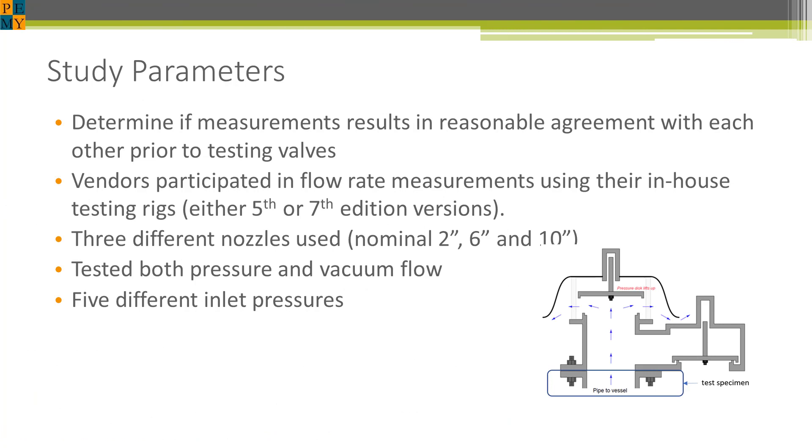Here you can see the flow nozzle that was tested. It's marked test specimen. We did not test the PV valves. It is nothing more than a machined orifice. There was a mix of 5th edition and 7th edition vendor test rigs due to their normal practice in certifying flow curves.